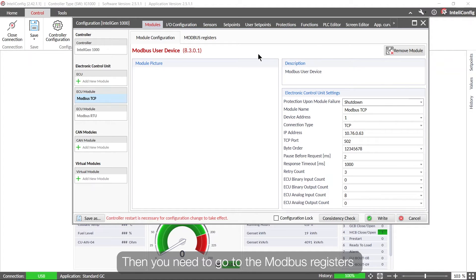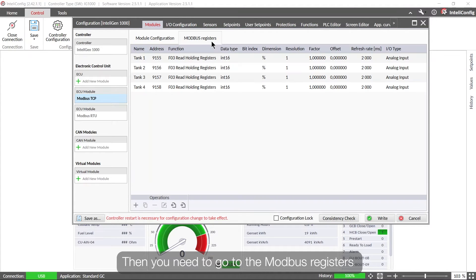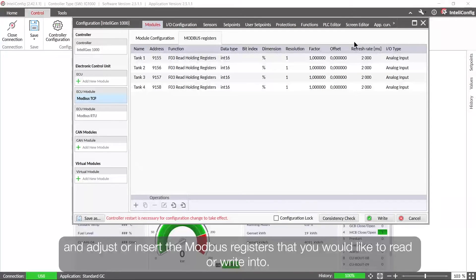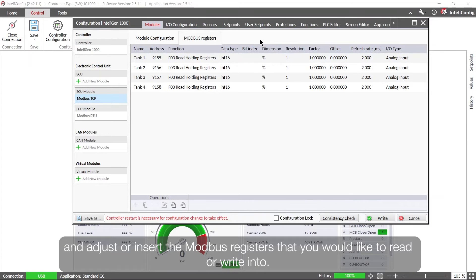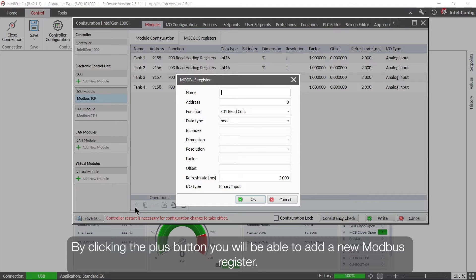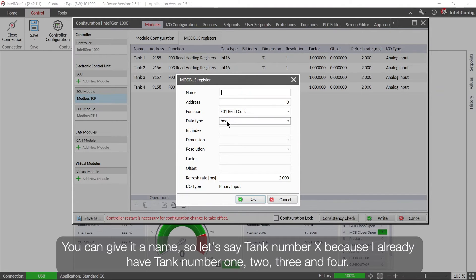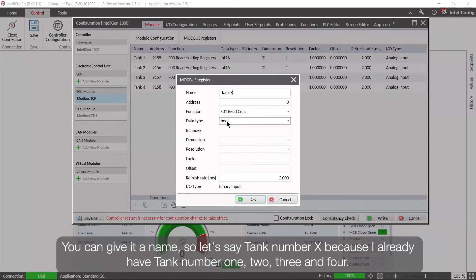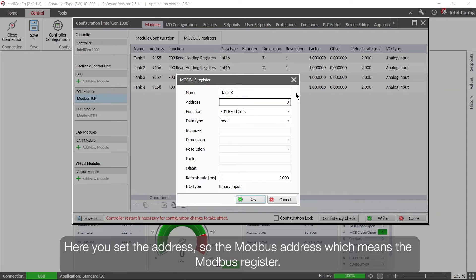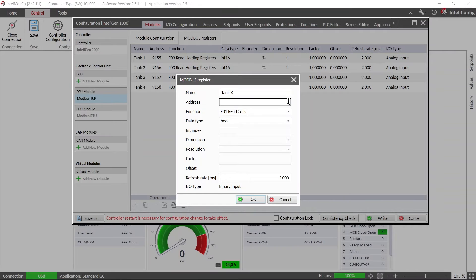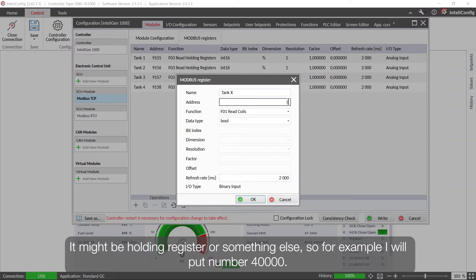Then you need to go to the Modbus registers and adjust or insert the Modbus registers that you would like to read or write into. So by clicking the plus button you will be able to add a new Modbus register. You can give it a name, so let's say tank number X because I already have tank number 1, 2, 3 and 4. Here you set the address, so the Modbus address which means the Modbus register. It might be holding register or something else.